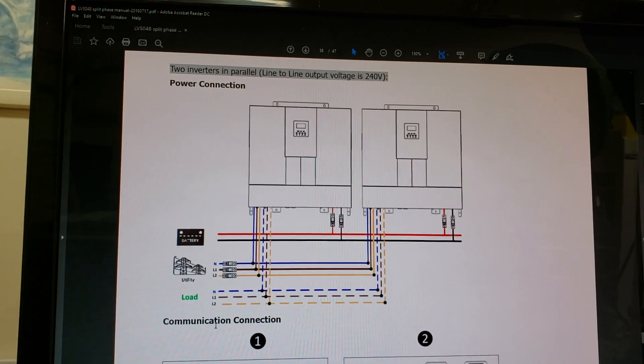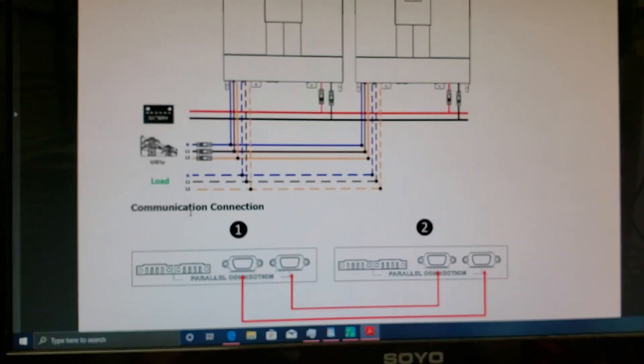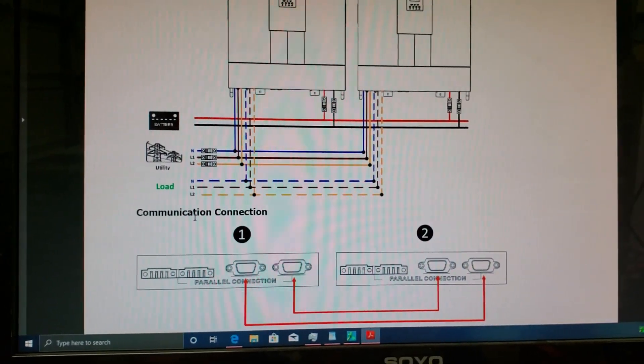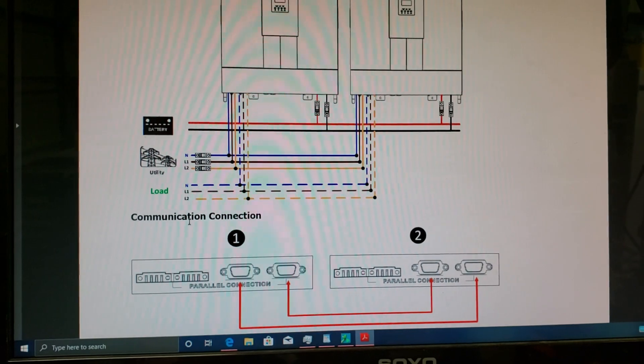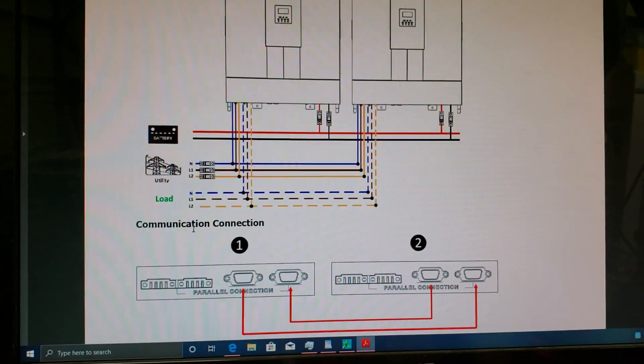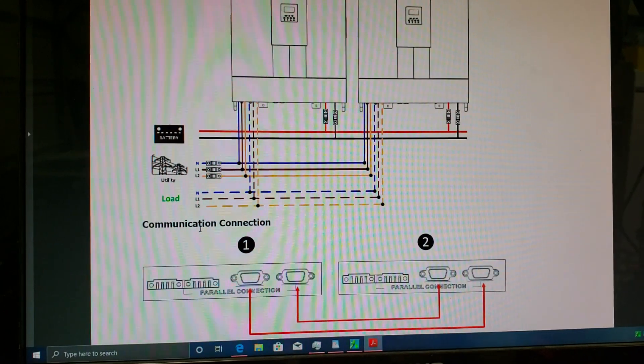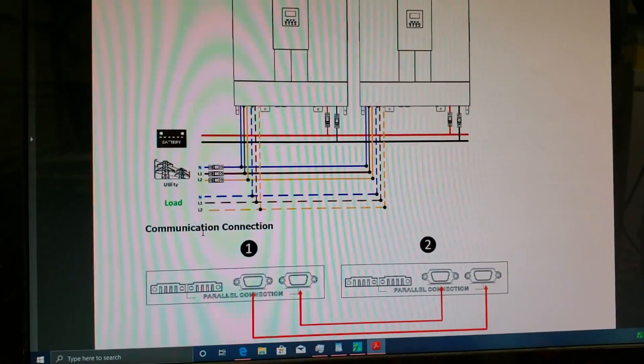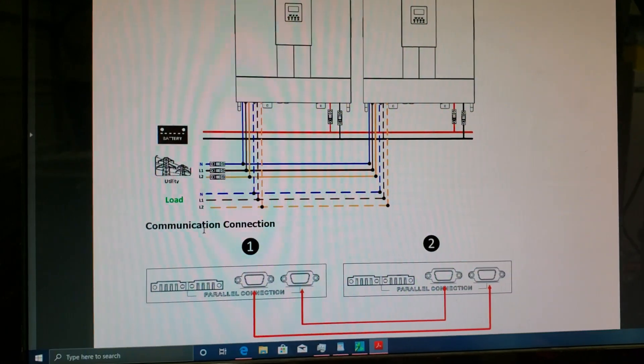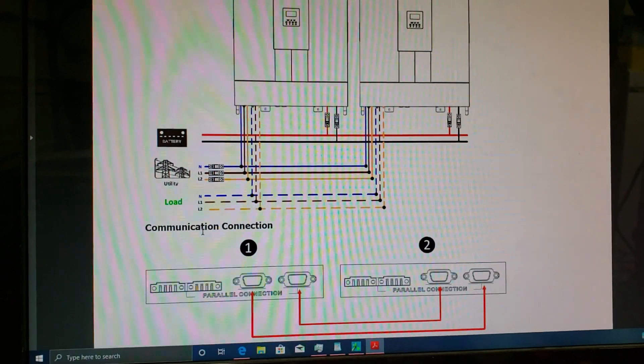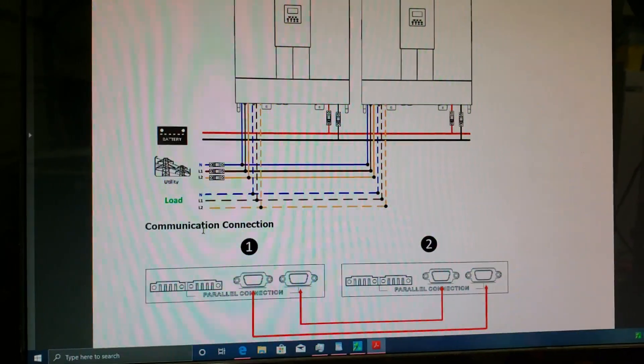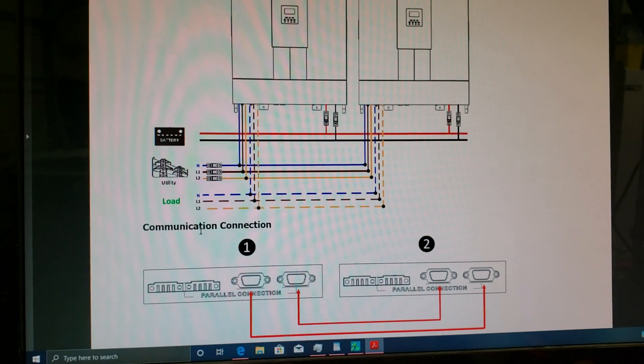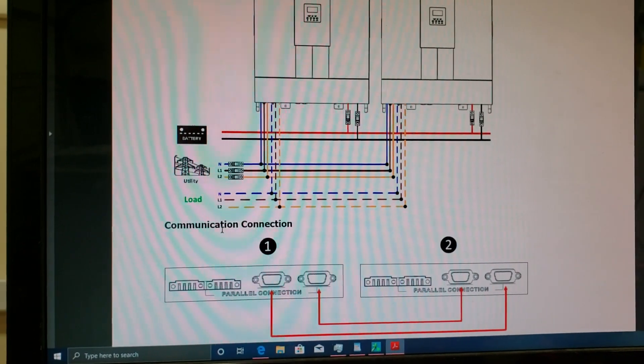Down on this portion is the communication connection. If you're looking at your inverters hanging up on the wall from the bottom side, on the left you'll see your first inverter and on the right your second inverter. You have two parallel ports on the right side of the inverter. Inside two has to be connected together and the outside two has to be connected together.